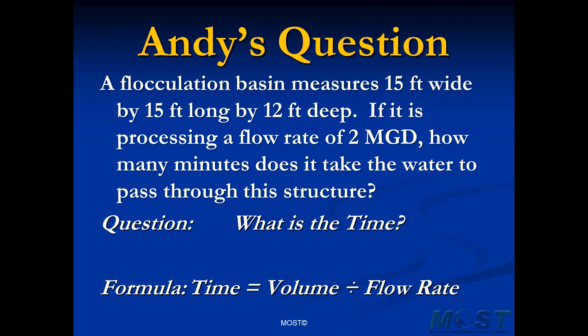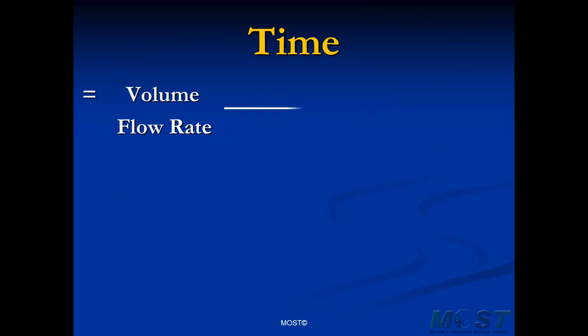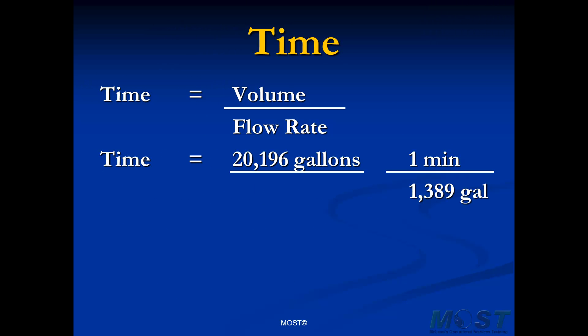Back to Andy's question. We have now found the volume of our flocculation basin and converted our flow rate into the proper units. So we can go to our final calculation — the calculation of time. That will be volume divided by flow rate: 20,196 gallons divided by 1,389 gallons per minute. Dividing by a fraction is the same as multiplying by that fraction inverted, so 1,389 gallons per minute becomes 1 minute per 1,389 gallons. The gallons cancel, time is left in minutes, and 20,196 divided by 1,389 gives us 14.5 minutes.